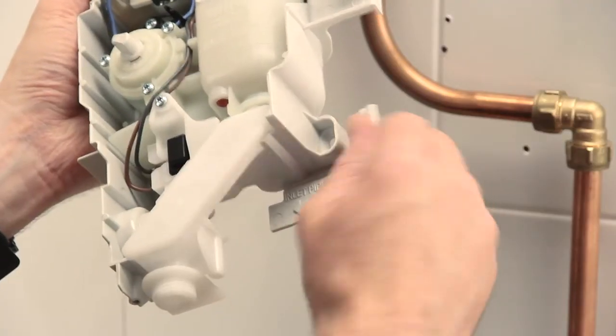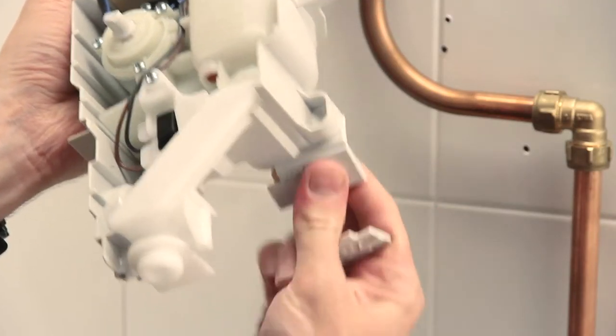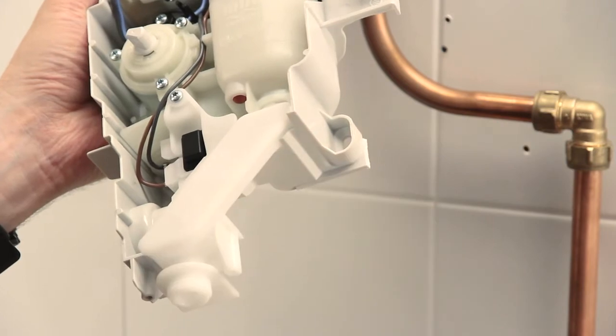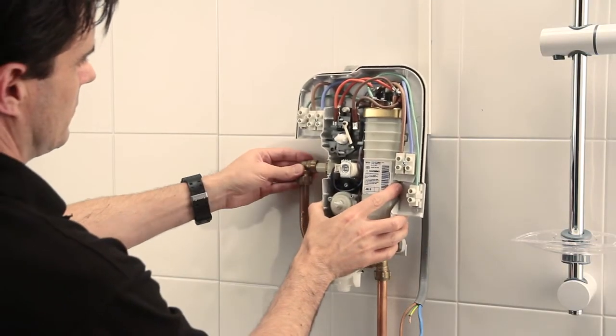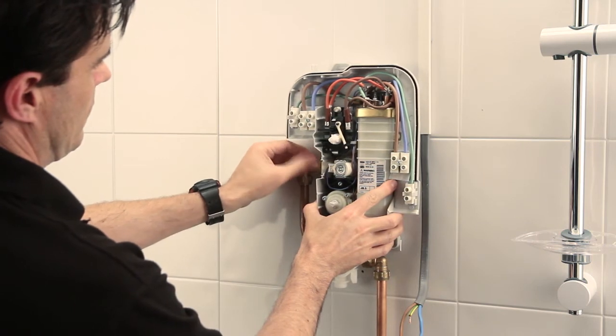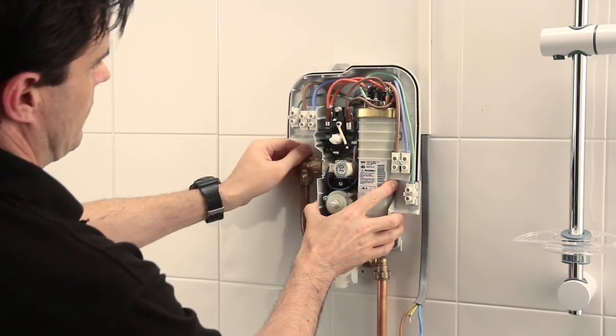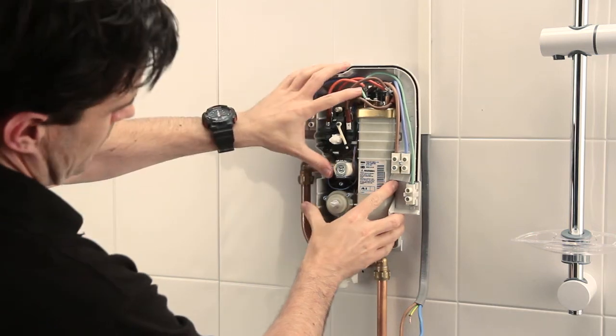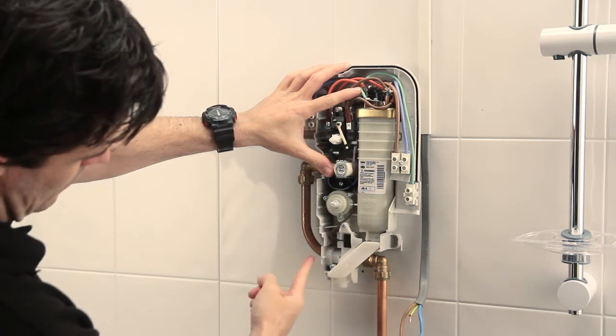Take the case and snap off the sections that are provided for ease of installation and hold the unit against the wall. Loosely connect the inlet supply pipe to the inlet connector using a push fit elbow or an elbow with a compression nut and olive. Notice that the integrated pipe channel discreetly channels right hand entry piping.